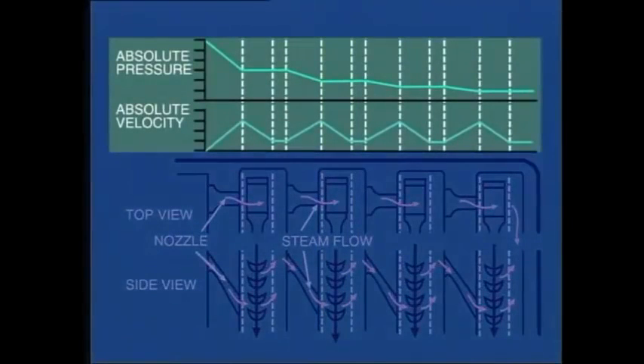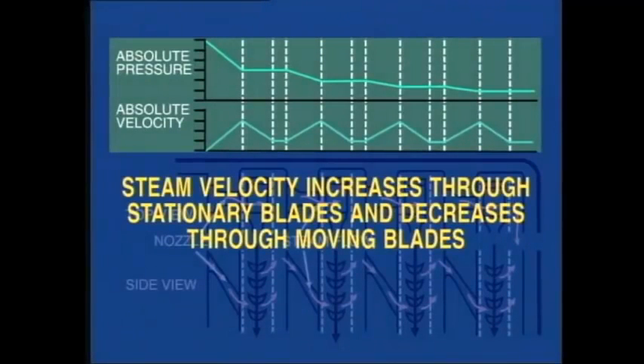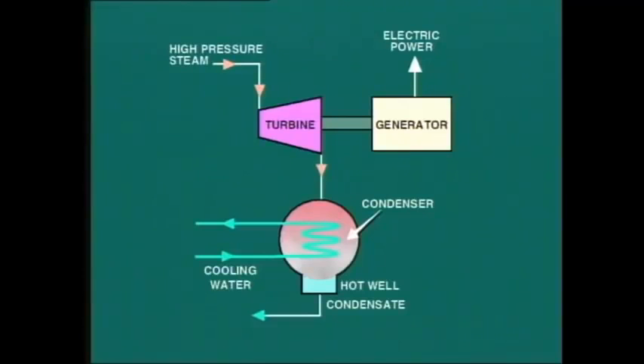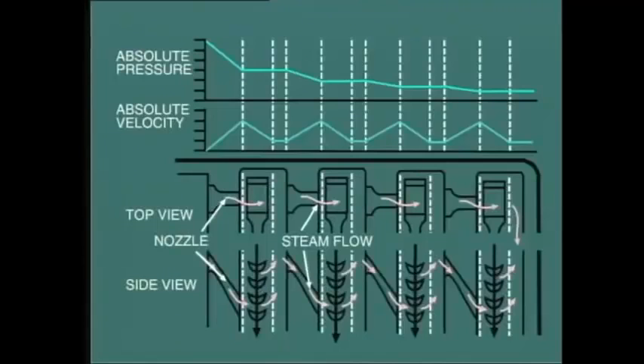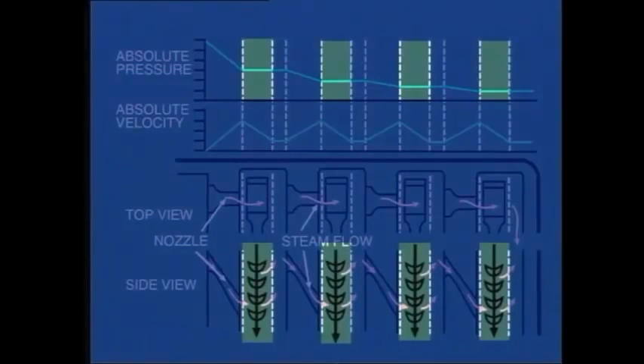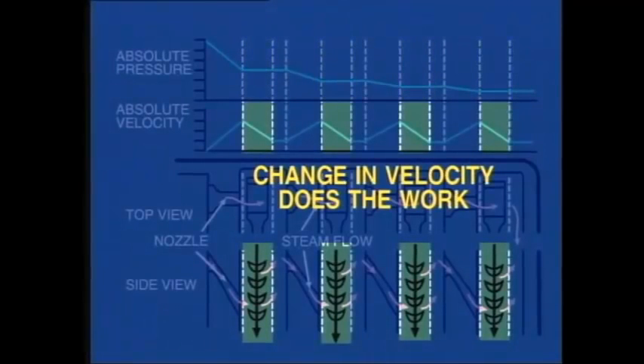We can see that as a result of pressure drop, the velocity of the steam increases each time it passes through a set of stationary blades, but the velocity then decreases as the steam passes through the moving blades and gives up energy. Eventually, when the pressure has fallen to a low value, it can no longer expand and produce work, and it is exhausted from the turbine. But look what happens here to the pressure as the steam passes through the moving blades. It does not decrease, neither does it increase. In fact, the pressure across the moving blades remains the same. It is the change in velocity which actually does the work and provides the energy to drive the turbine.